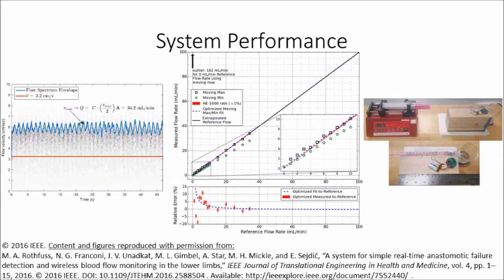The system was benchmarked using a syringe pump, which is accurate to within 1%. Flow rate and velocity were computed from the spectrogram of the measured blood flow signal. The measured performance showed a relative error less than plus or minus 5% above 8 milliliters per minute, and about plus 1.2% to minus 0.8% at its upper benchmarked flow range. To the best of the author's knowledge, this accuracy is the lowest reported in wireless implantable blood flow monitor literature across its benchmarked flow range.